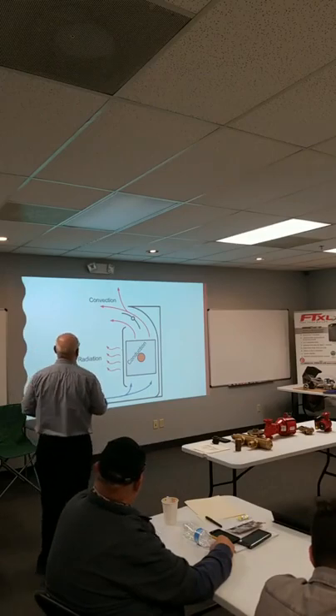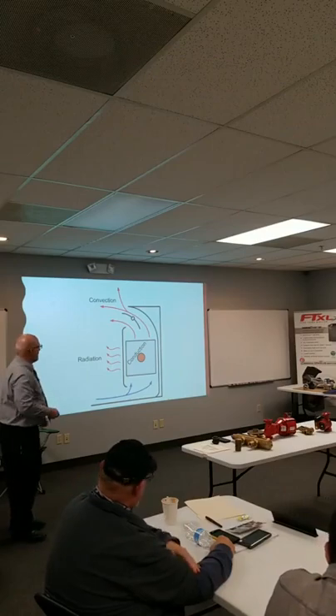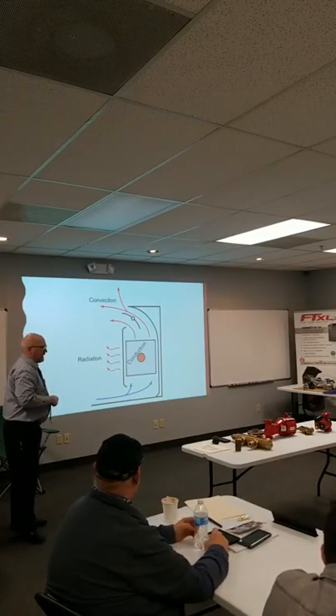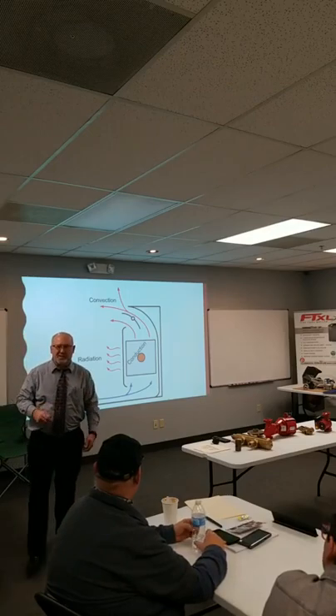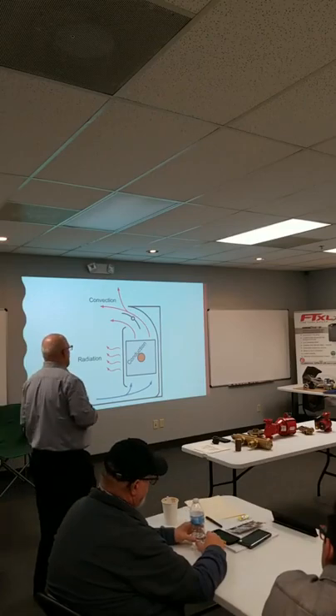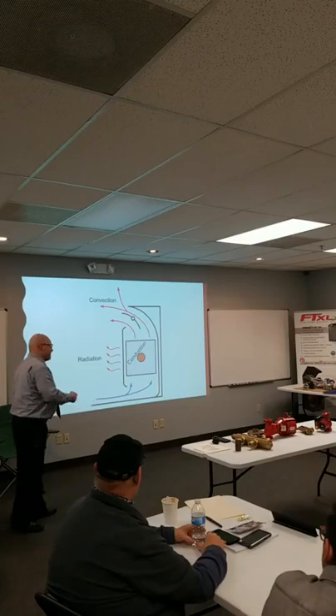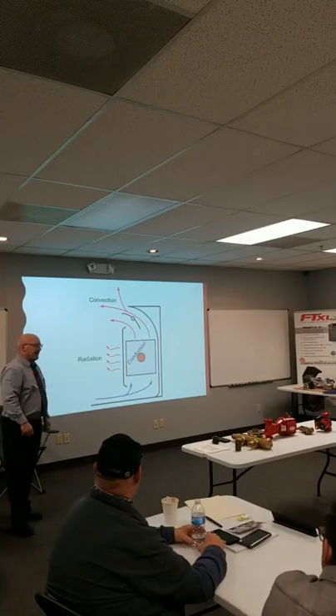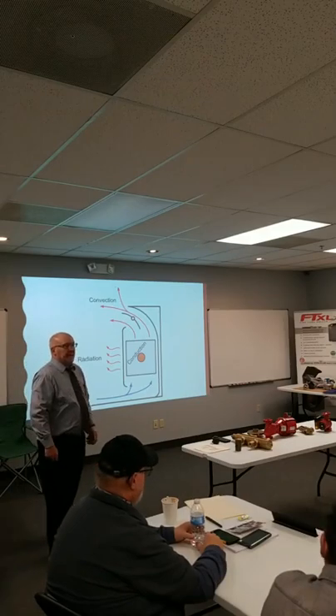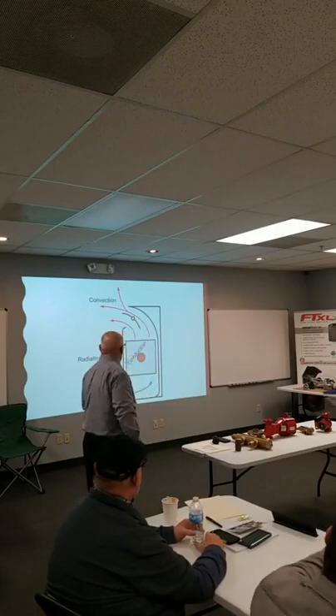We need that convection. We need that air coming up to take that heat and transfer it out. And again, the damper on a radiator, you go out there and see that it's closed, and they complain that they don't get the room up to temperature. There are a lot of things we have to be aware of, and I tell people all the time, slide your bed out of there, pull your dresser out. I don't like it there. Well, then freeze. I can't help you. We can put more radiation all over the place if you want.